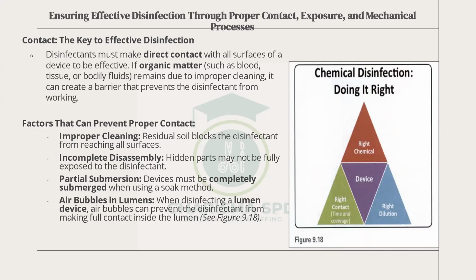Okay, so ensuring effective disinfection through proper contact, exposure and, of course, the mechanical process. Now, there are some factors that make the disinfection process effective or ineffective. Contact, organic matter, very key. Now, we just learned that the peracetic acid requires 5 minutes. So if you use 4 minutes, no. We saw that the glutaraldehyde, not the ortho-phthalaldehyde, we are talking about the glutaraldehyde, can lead to sterilization in 10 hours. So even if you soak the instrument in it for 9 hours, 58 minutes, no, the contact time is not reached. Just 2 minutes short of the 10 hours, no. So the 10 hours must be reached.